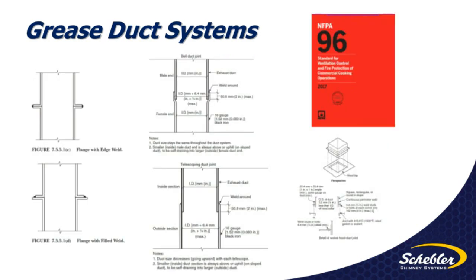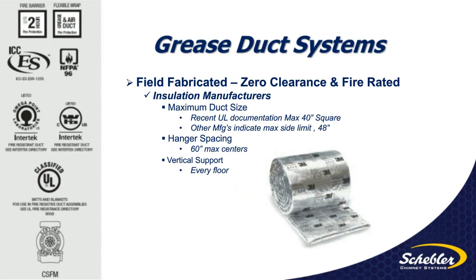Now, NFPA 96 is going to give you a little better example of acceptable weld joint types, whether it be flange with edge welds, fillet welds, bell-type overlapping joints, and then some pretty detailed construction of how you would construct the ductwork to the hood itself to be considered acceptable to NFPA 96. Another source for construction of ductwork would be the information published from the insulation manufacturers.